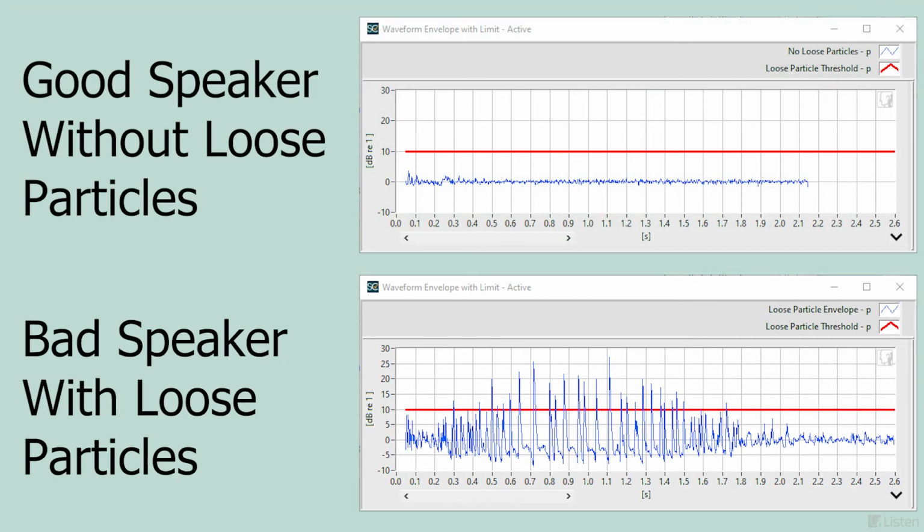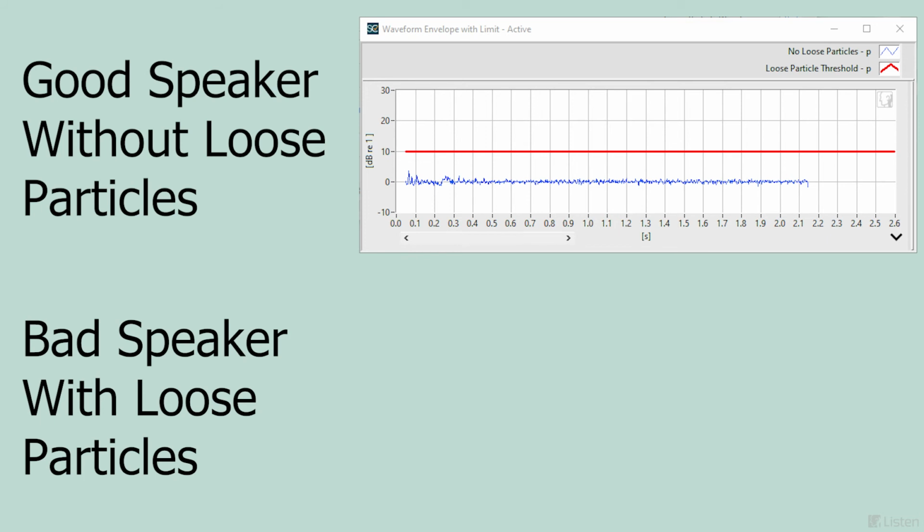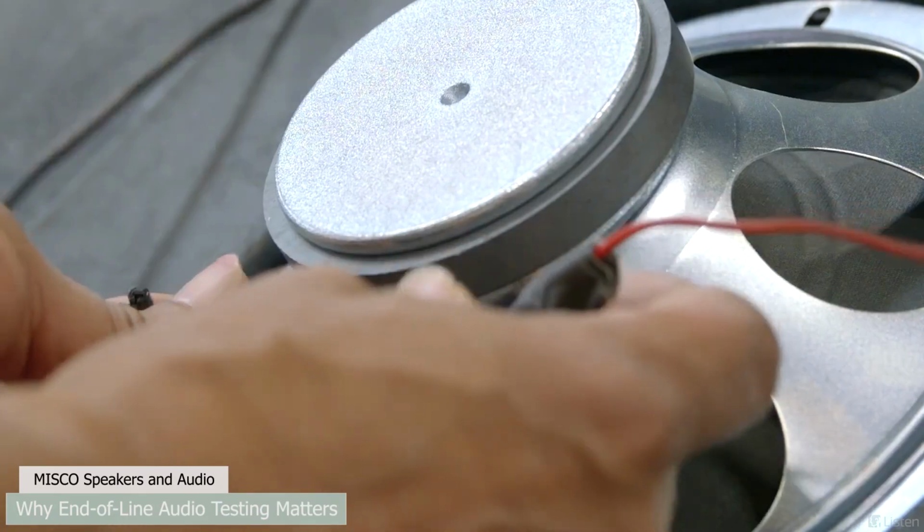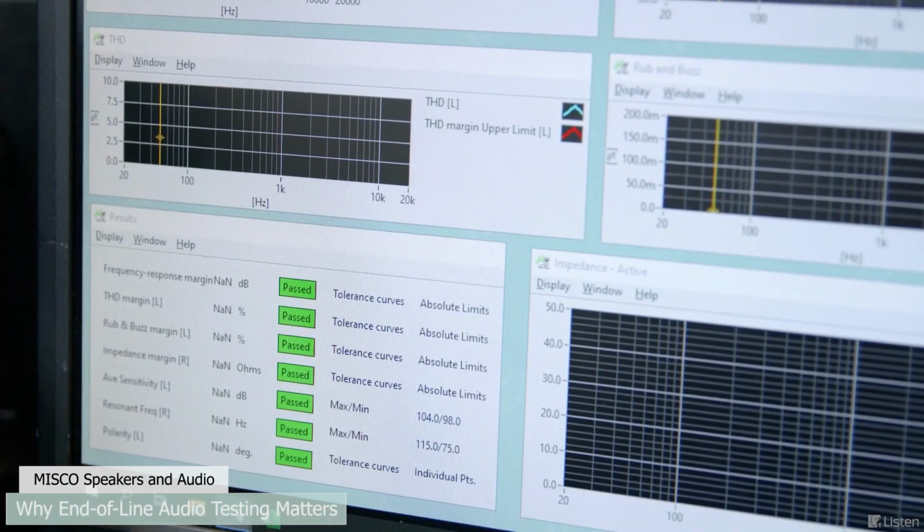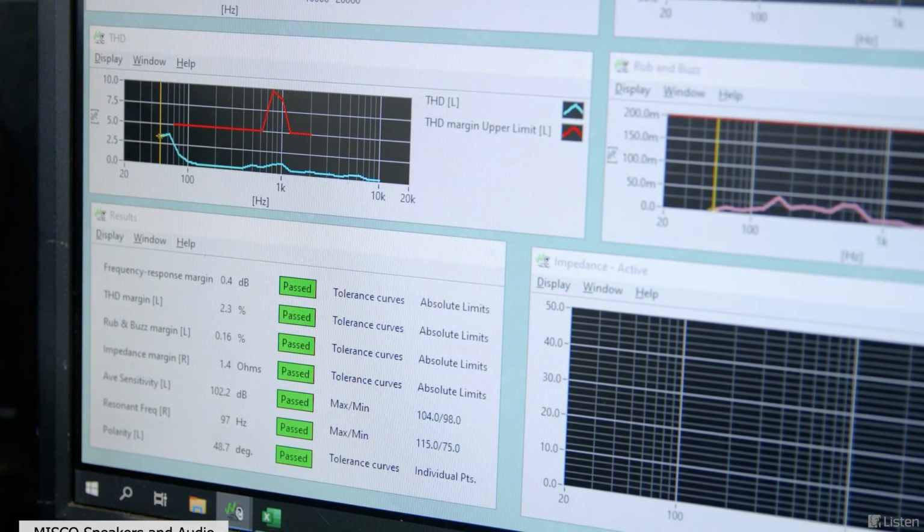Measuring the different types of distortion enables rapid troubleshooting and correction of manufacturing problems, and Soundcheck is the only production line measurement system that can accurately distinguish between periodic and random transients. Loose particle detection is also useful for identifying loose or rattling components such as buttons, keyboards, wires, and fasteners. In the digital domain, it can catch Bluetooth dropouts, clipping, and other digital signal processing artifacts.